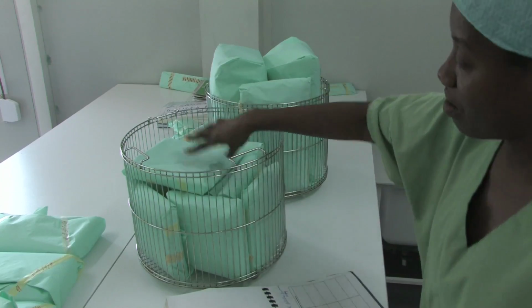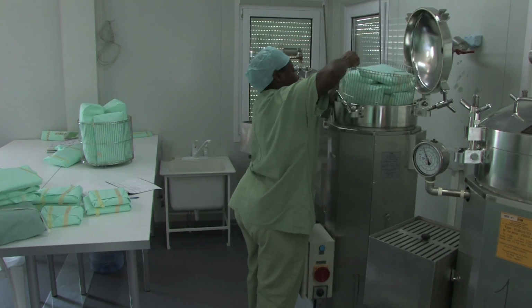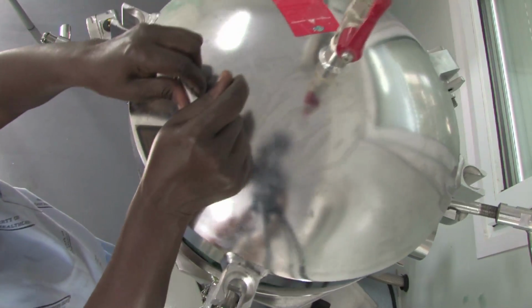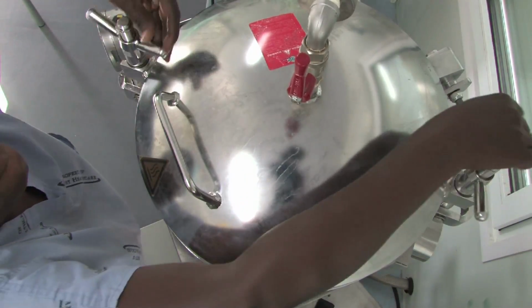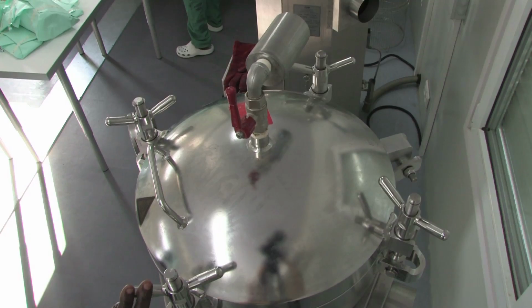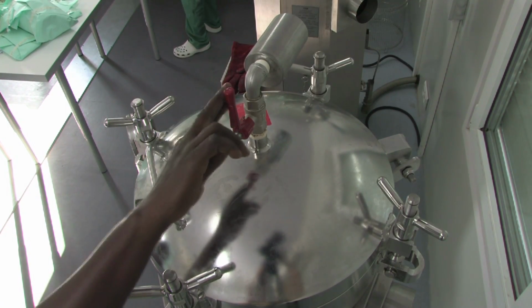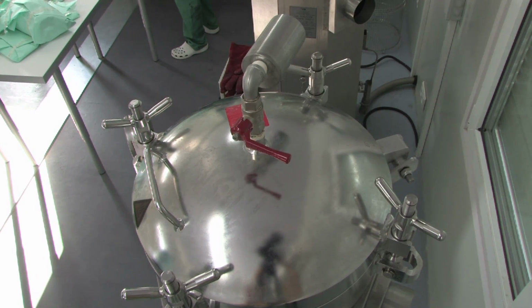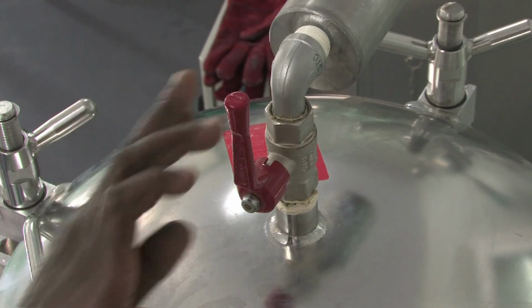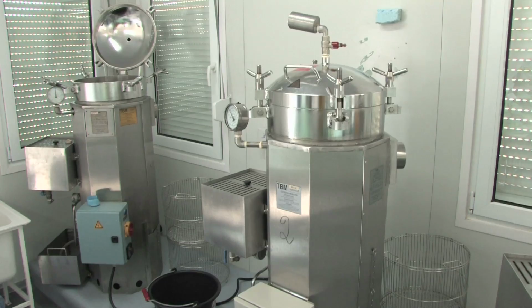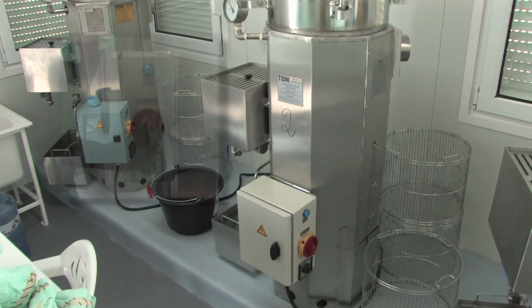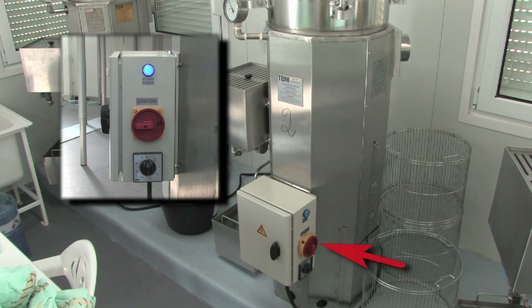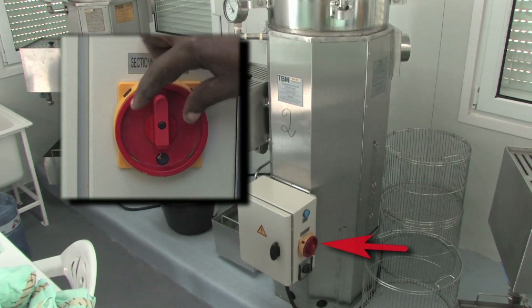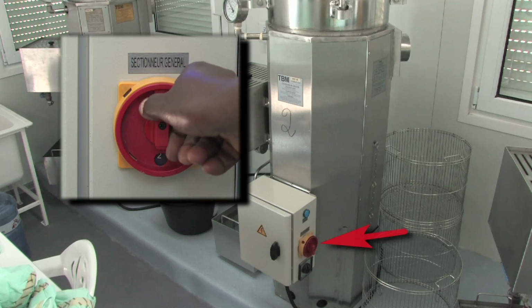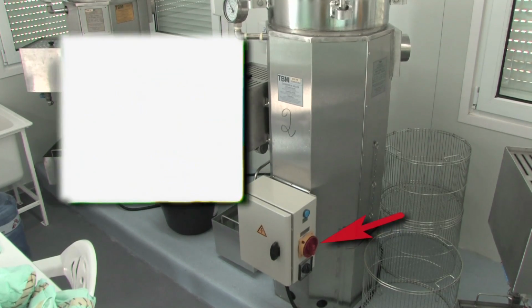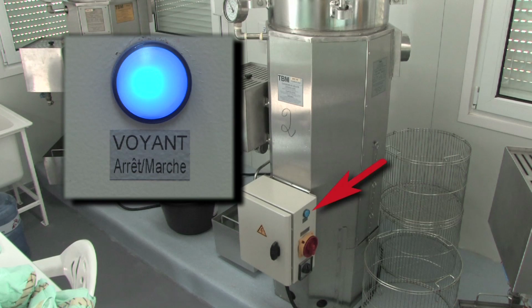2 metal baskets are used to load the autoclave. The cover is equipped with a seal to ensure that it's watertight once the wing nuts are tightened down. A red air inlet valve is used to bring the autoclave back to atmospheric pressure so that it can be opened when the sterilization cycle is over. A switch on the electrical box is used to set the heat level from 0 to 3. When the switch is in position 1, 2, or 3, an indicator light shows that the autoclave is turned on.